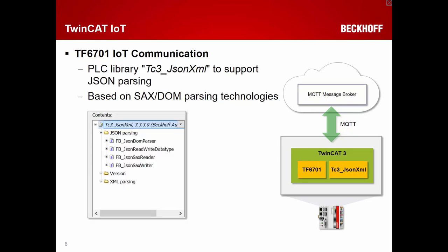When publishing or receiving data, you can use binary format for efficiency, or JSON format. A dedicated PLC library supports JSON parsing within your PLC logic using SAX and DOM parsing technologies to handle JSON messages. This library is also available within the latest TwinCAT 3.1 release, build 4022.0.